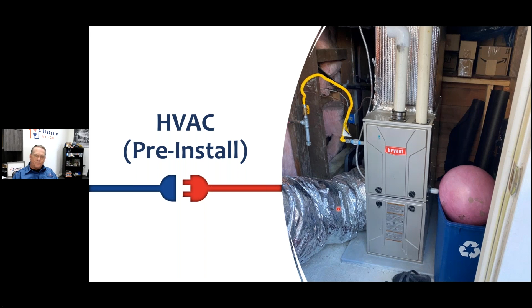We put in a system that was quite a bit smaller than this. This is the upstairs system, and I got a little corner of the furnace here. I couldn't find the picture of the whole furnace. This ductwork was not in bad condition, the vapor barriers were fine. We did take all the insulation off the Ys and reseal the entire ductwork, but when we did our load calc, the ducts were fine for what we needed to do.